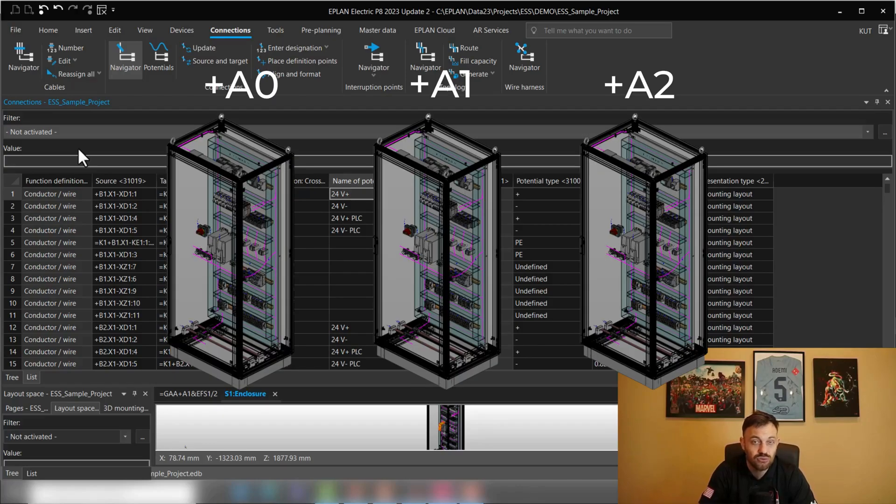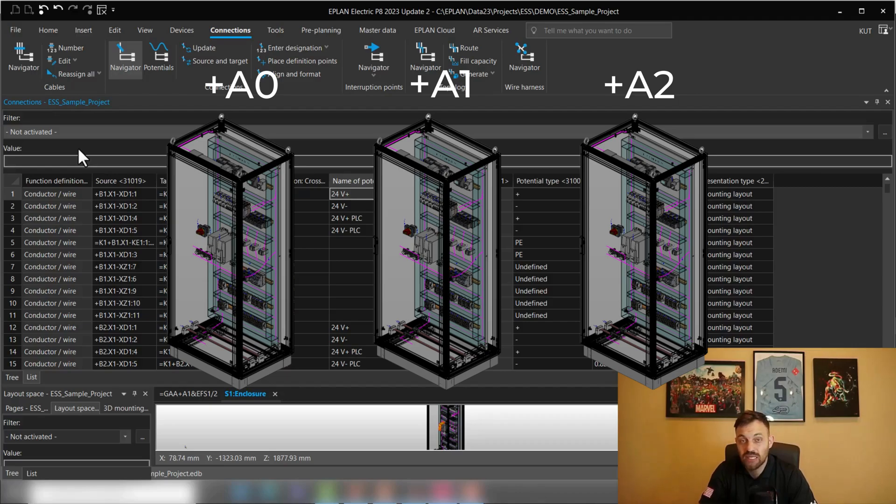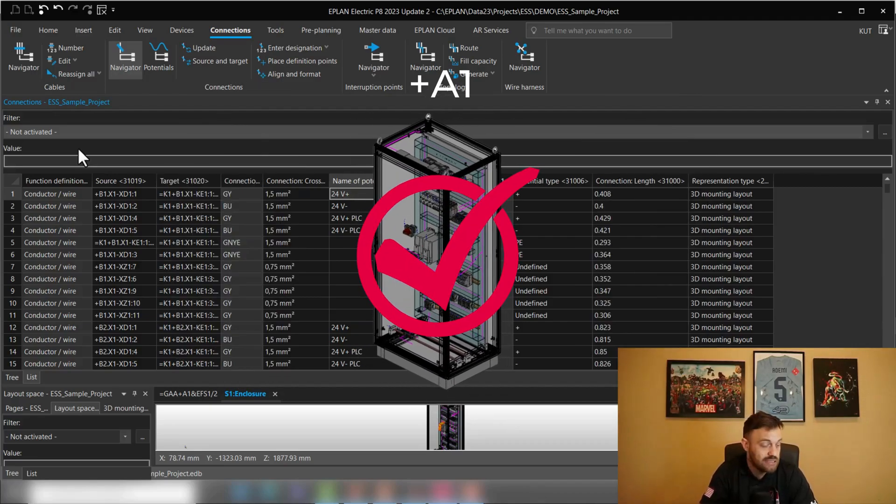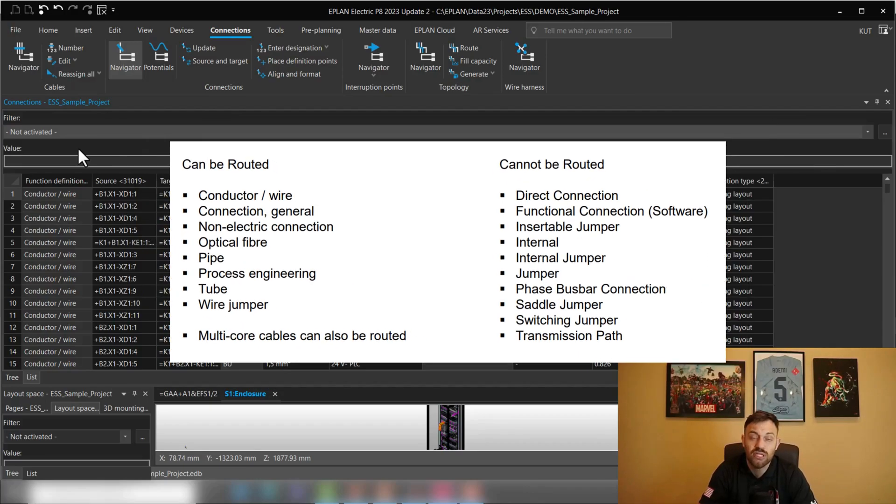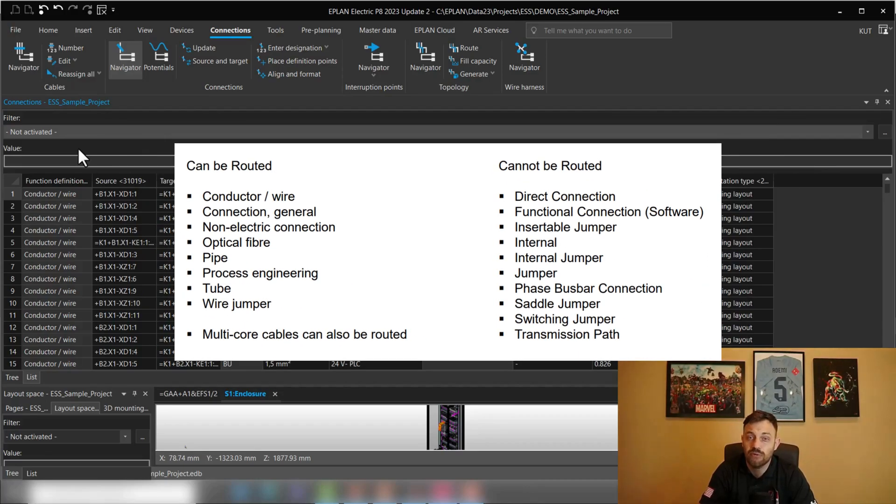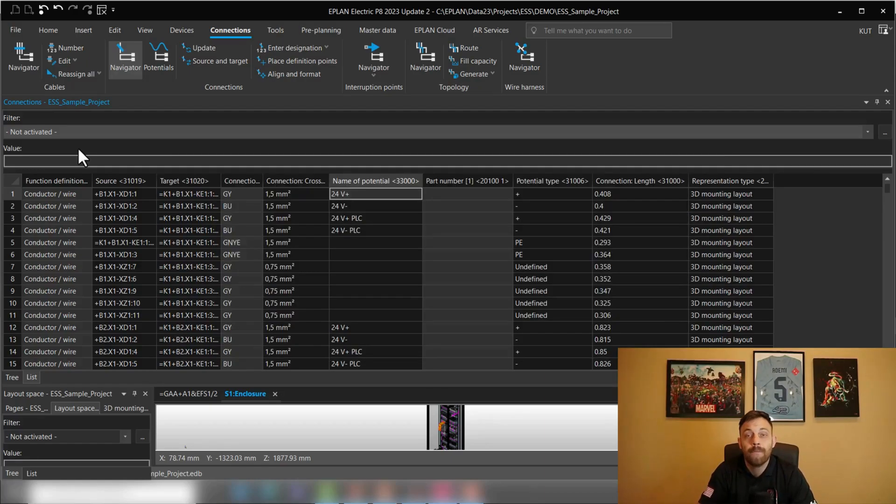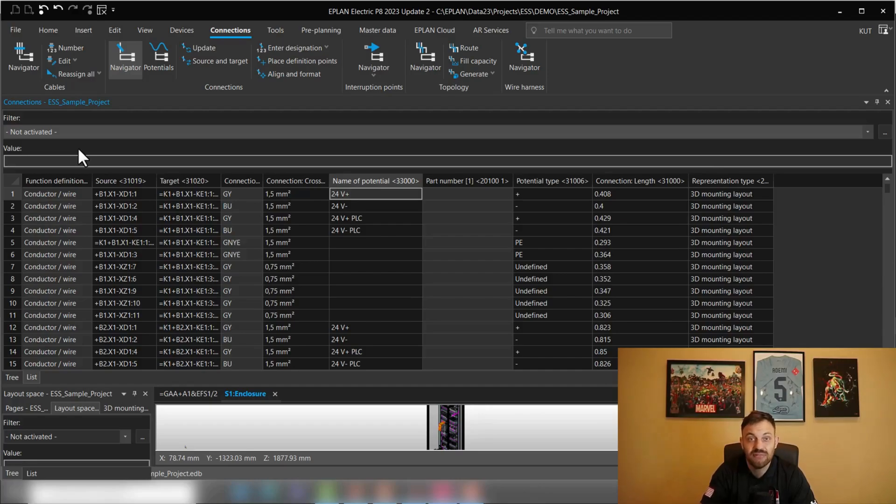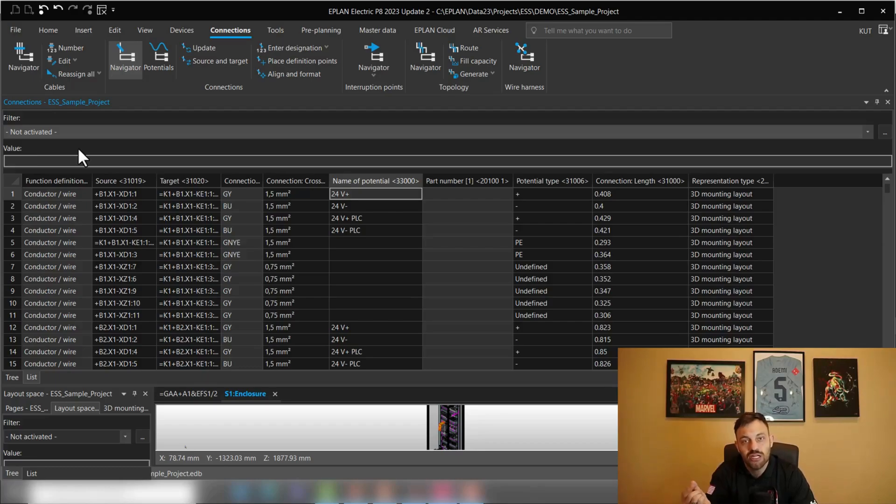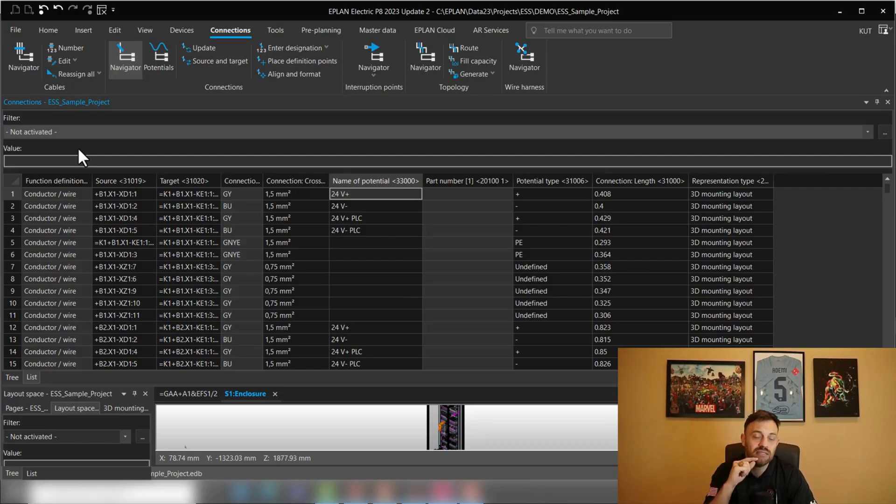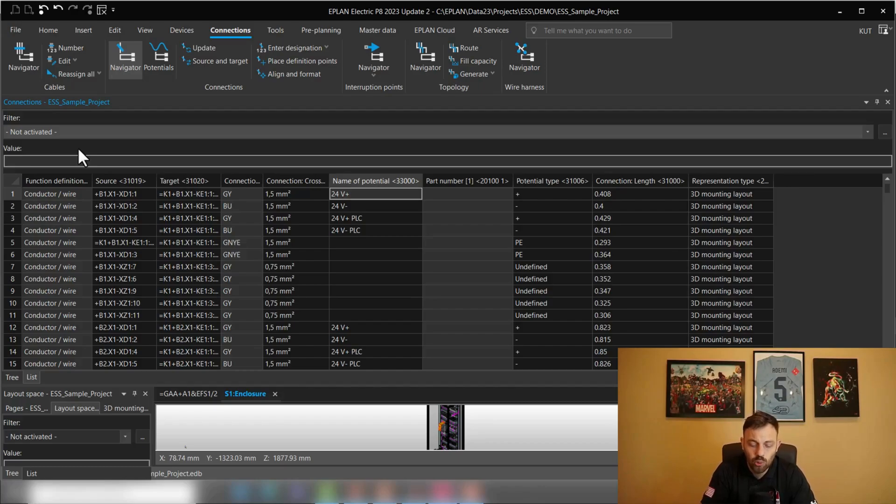So the filter should display us all wires which need to be in a certain location, for instance in a certain enclosure, like in this case enclosure A1, contains a routable functionality like connection, like wire, like tube for instance, and don't have a routing length yet. So that will be what we want to achieve, is to get the 3D length, but in the filter we will negate it. So if you know what the criteria are, then we could actually start to create a filter.